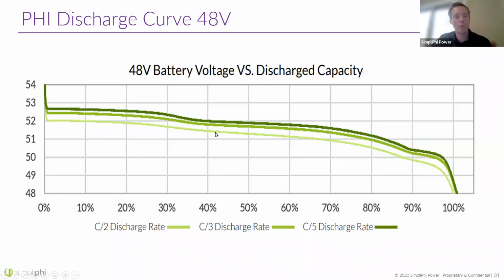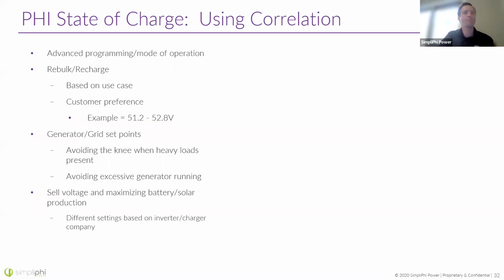Notice when we get down to a voltage of 50 volts, there's still 12% capacity remaining in that battery. If we were discharging at a slower rate, when we hit 50 volts, you would hit 5% remaining. So that's what I was talking about: if your battery's under heavy load, you hit that knee a little bit quicker.